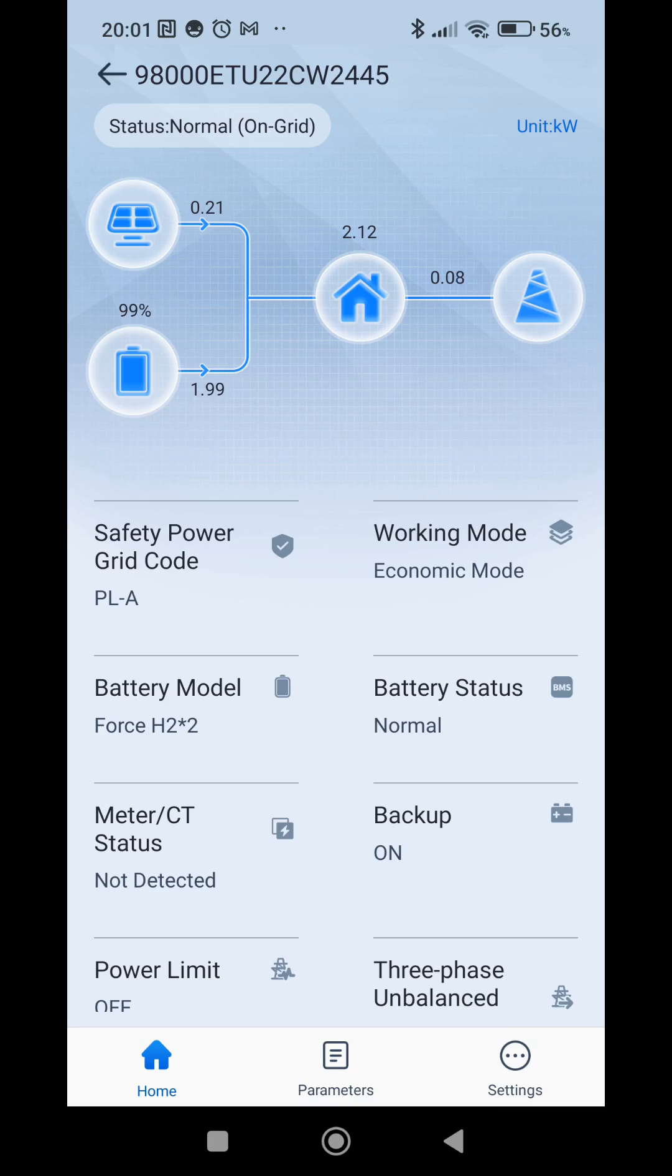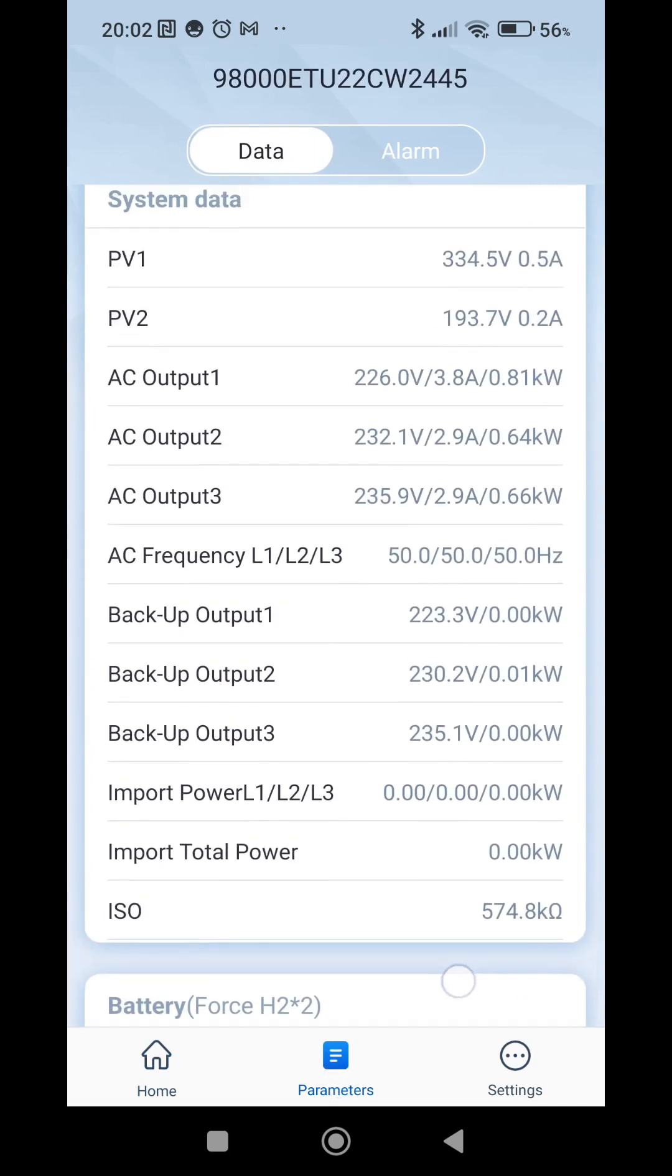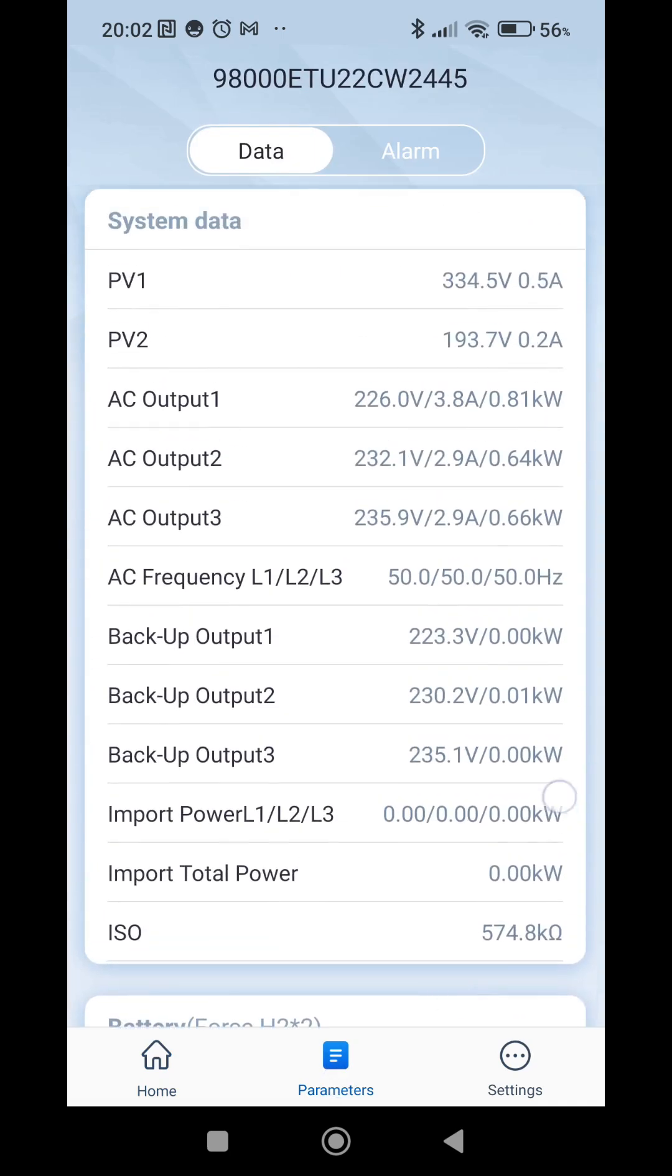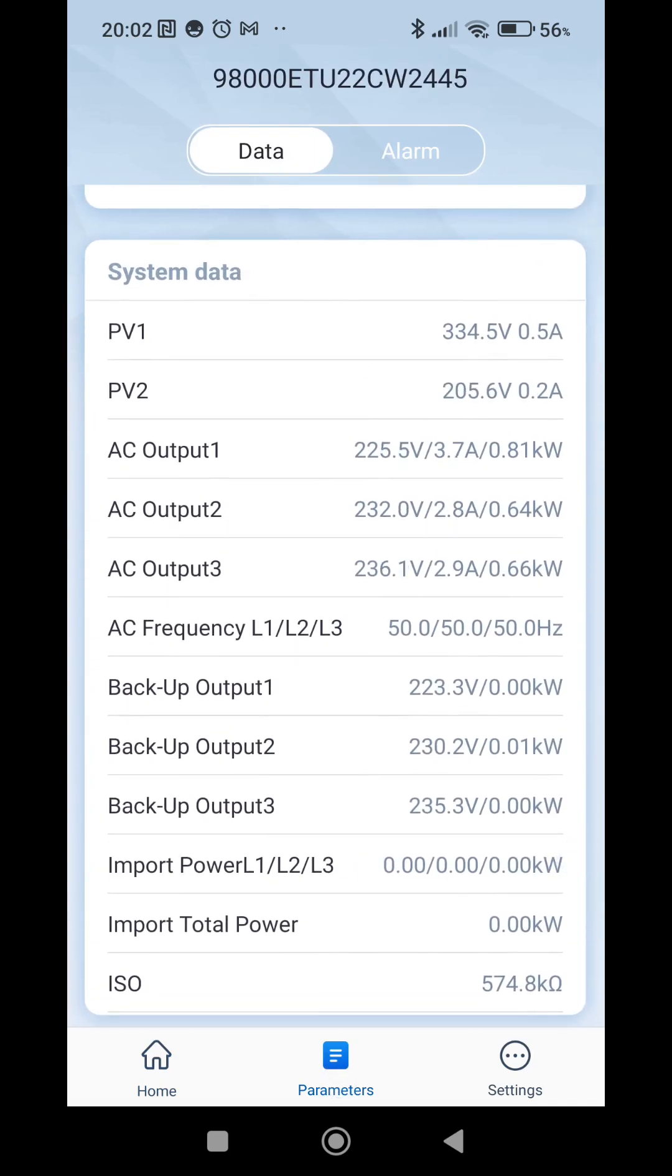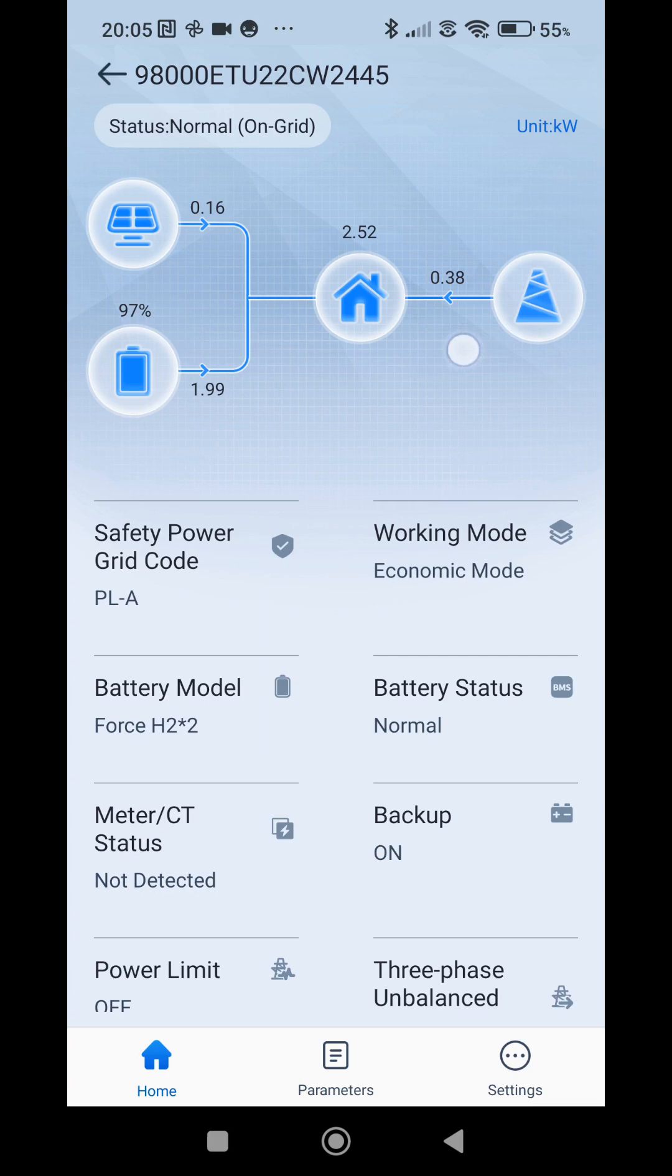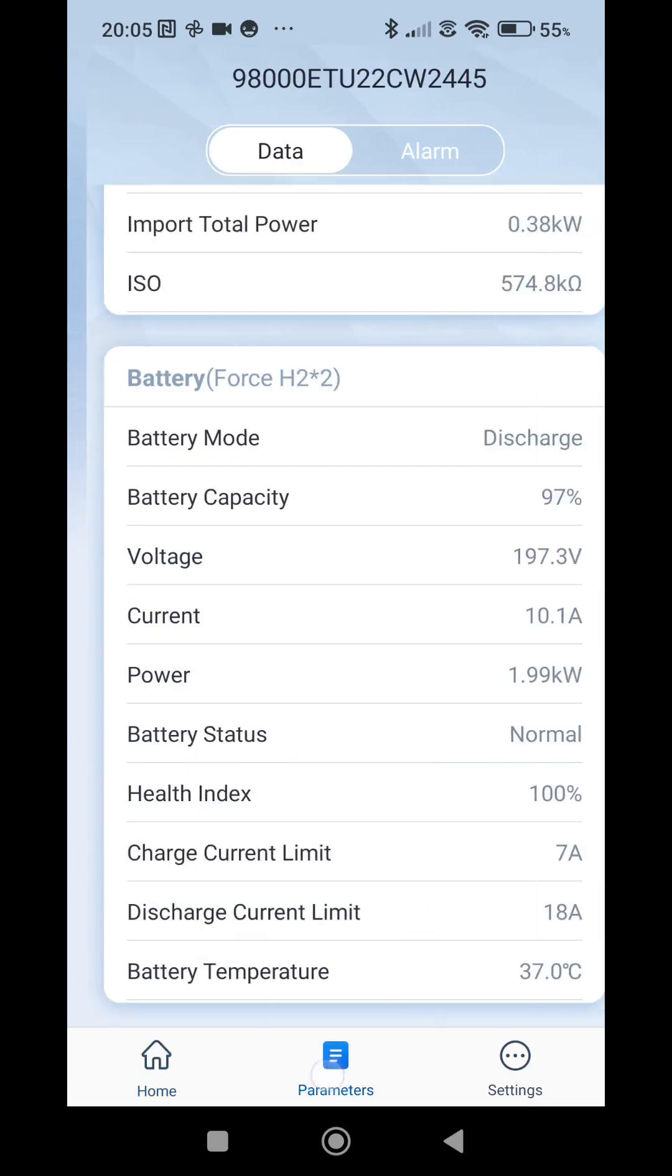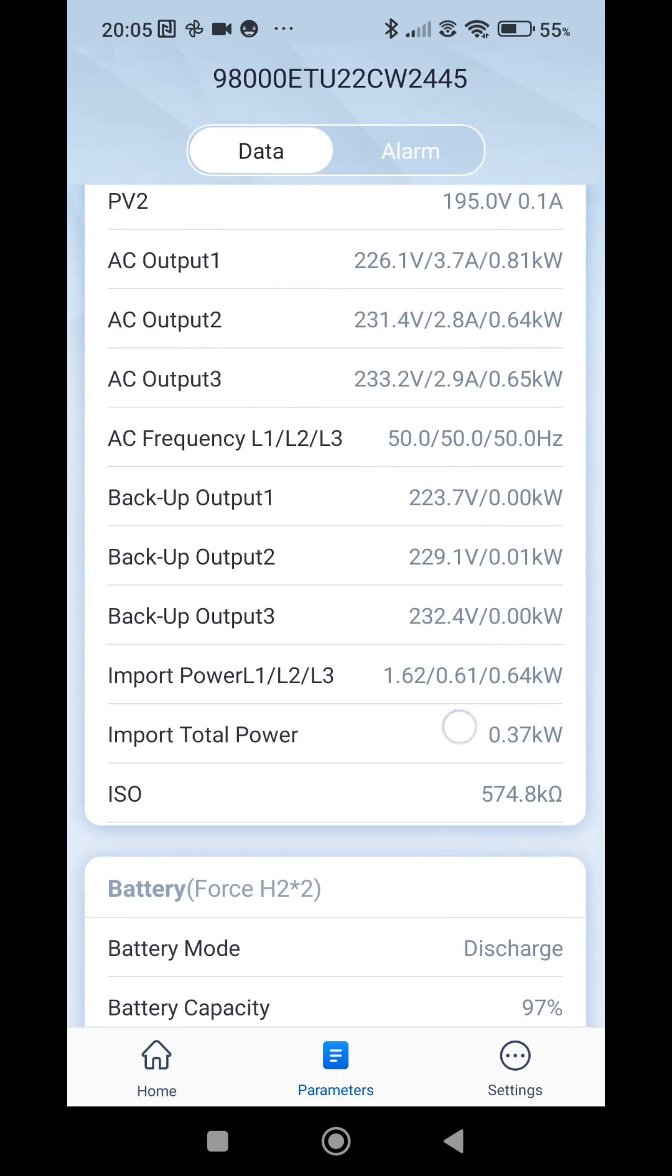We still have 200 watts from the solar power so we are not taking the electricity from grid. We can check it here. We have import power 0. But if the load increases more we will start to import power from grid. So this 2 kilowatt power from the battery is hard limit which doesn't change depending on the load.